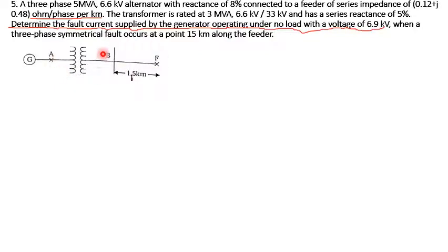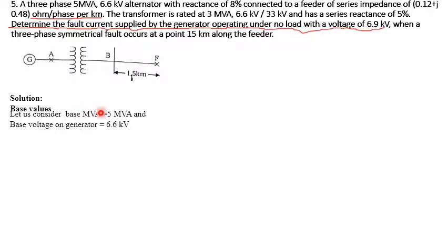This is a single-line diagram we have. First and foremost, we have to calculate the base values. In this chapter, we have to consider the highest MVA rating. The MVA base of the generator is 5 MVA and the transformer is 3 MVA, so we go with the generator. The voltage on the generator side is 6.6 kV.